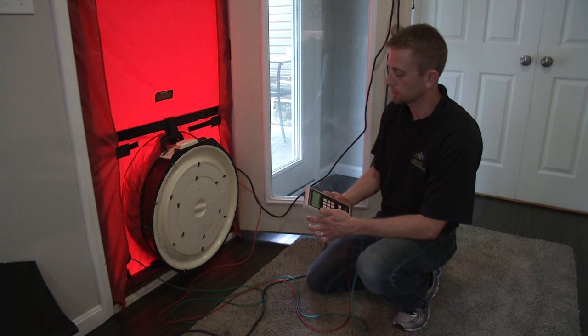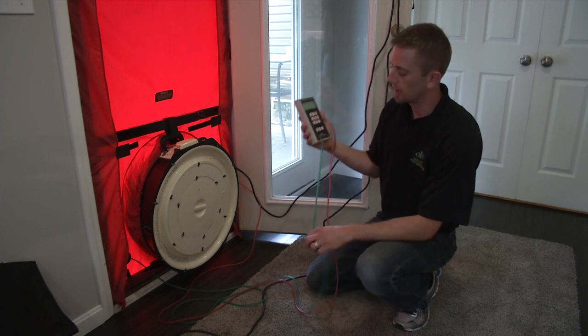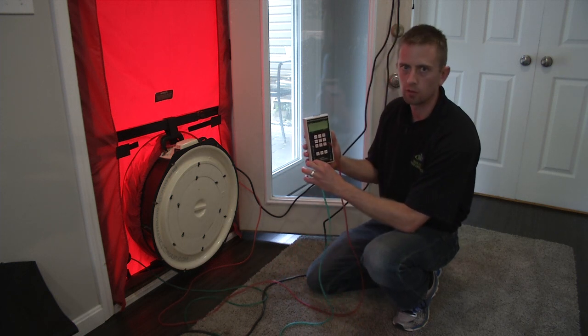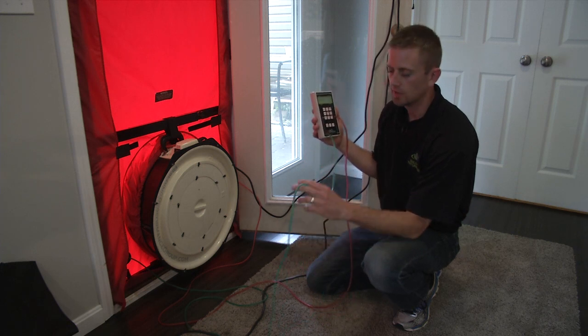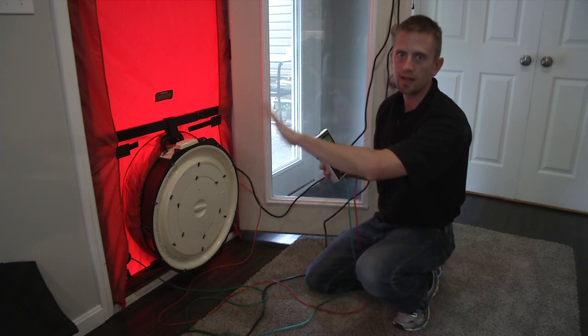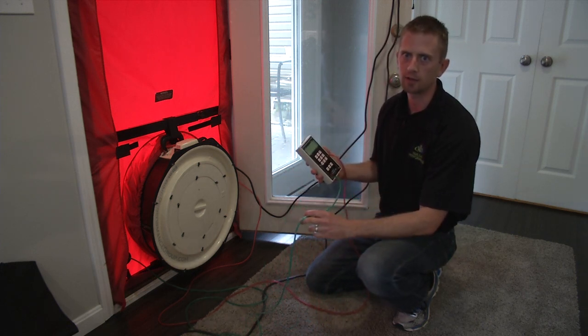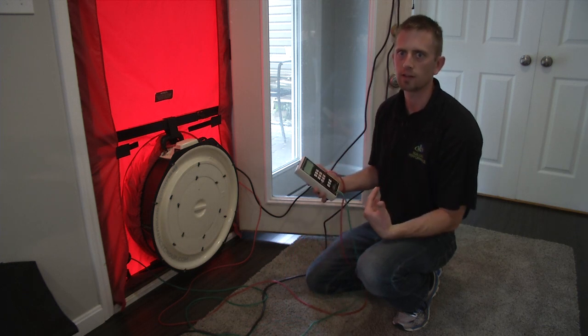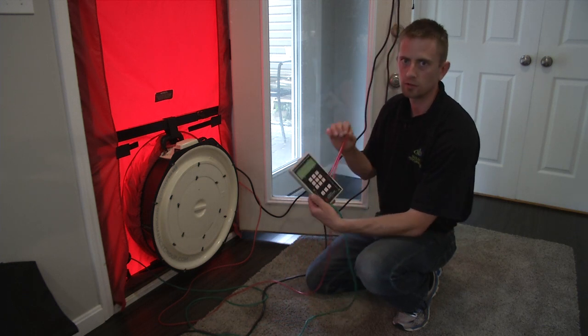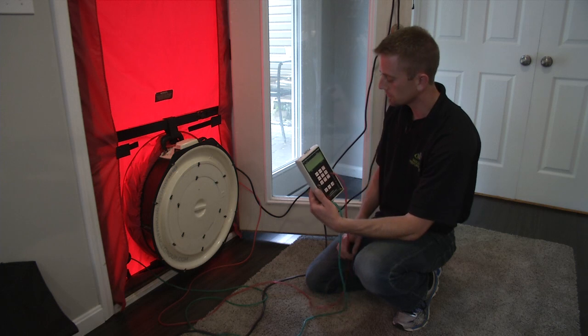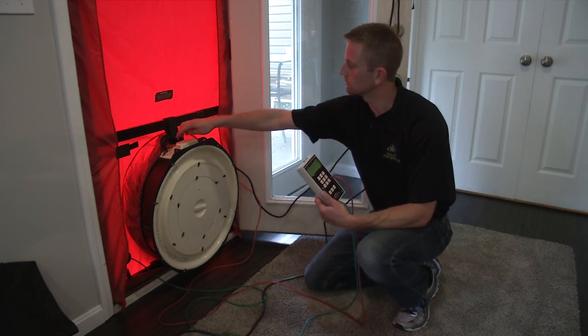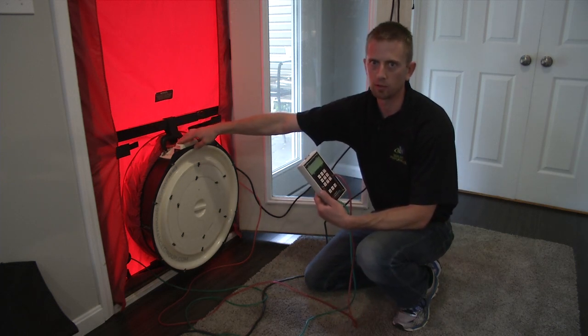So on the blower door, you've got another pressure gauge. You've got a green hose that's connected to the lower left-hand reference. This runs through the blower door to the outside, so that gauges my pressure to outside with reference to the inside of the house. The red hose goes on the upper right-hand corner tap and runs to your pressure tap right here on the top of the blower door.